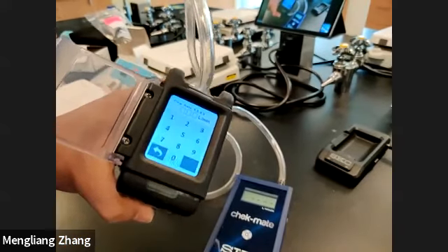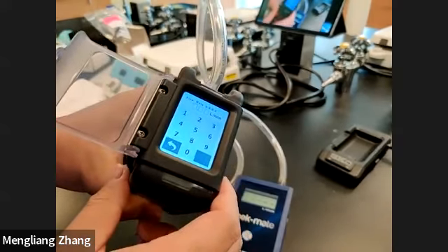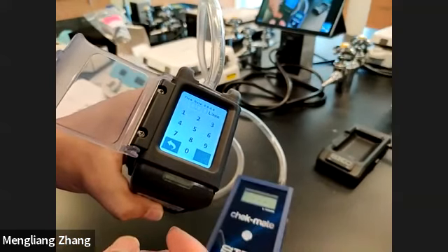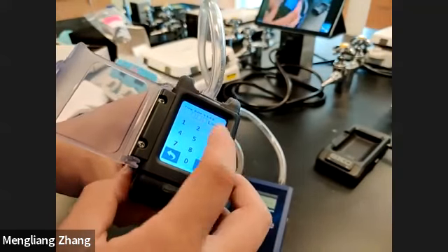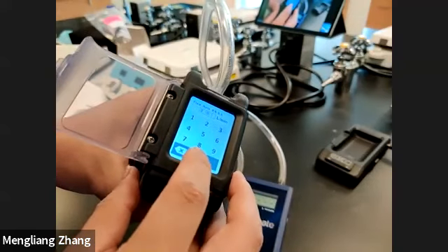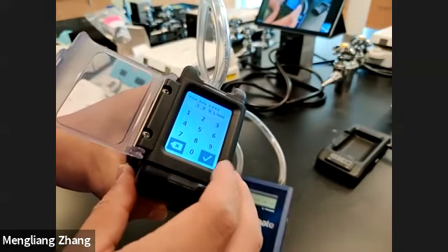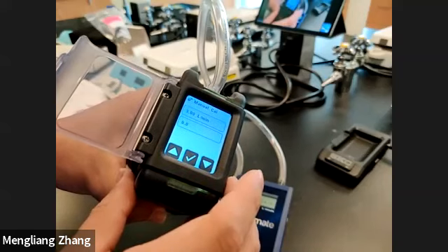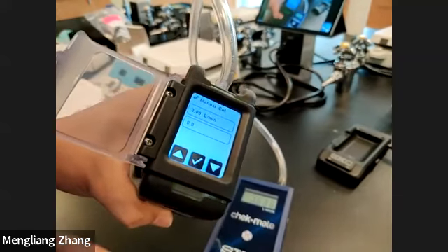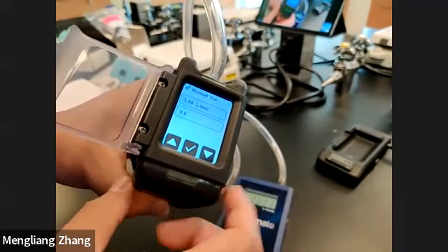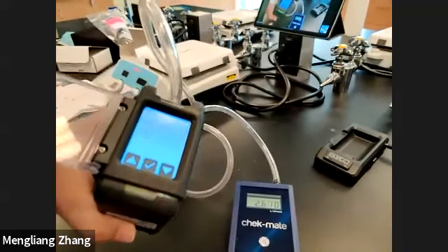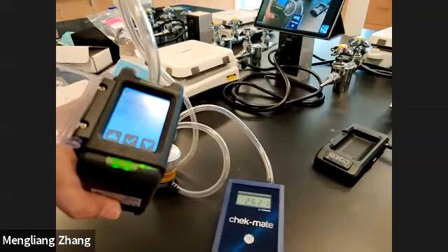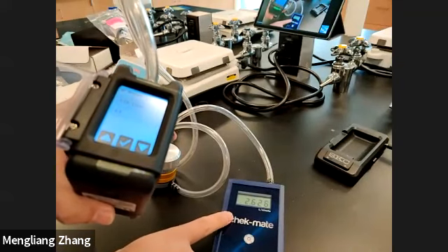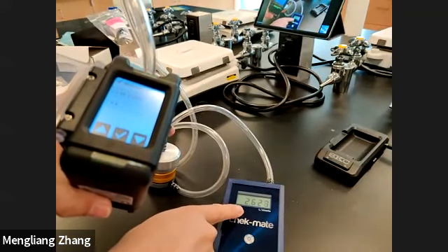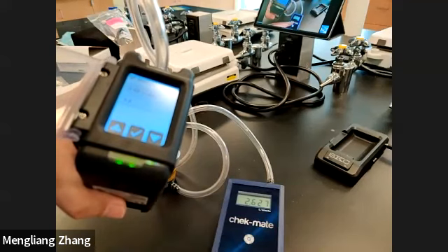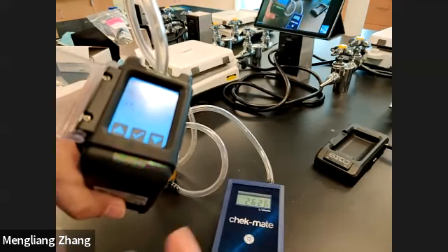First, you need to input the desirable airflow you want to calibrate. In this case, we want to use 3 liters, so 300. Okay, and then press yes. Then you will feel the vibration from the pump. You can see the real airflow; you can read it from this calibrator. Now the airflow is 2.627. It's not 3.00 liters per minute.